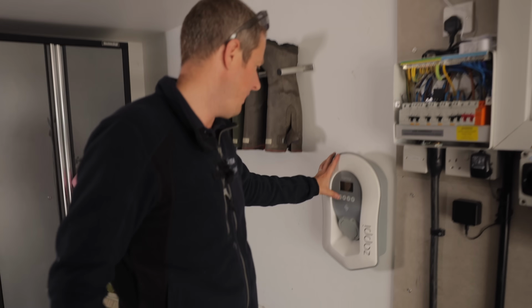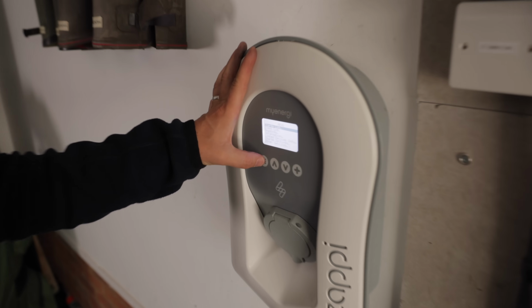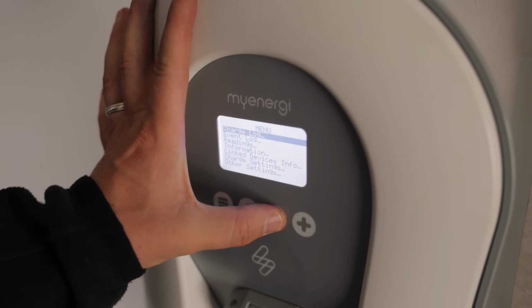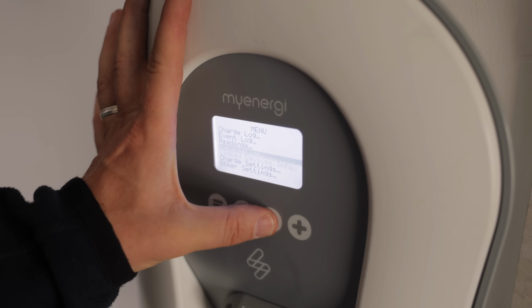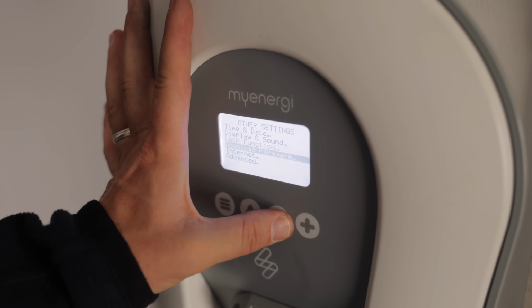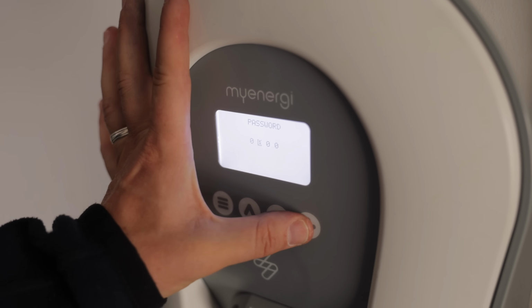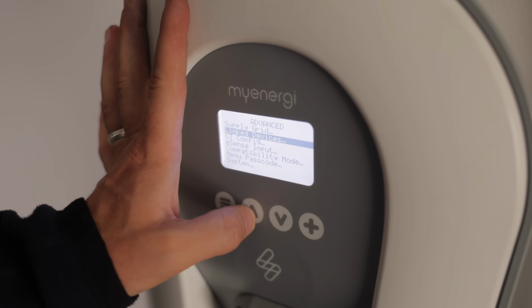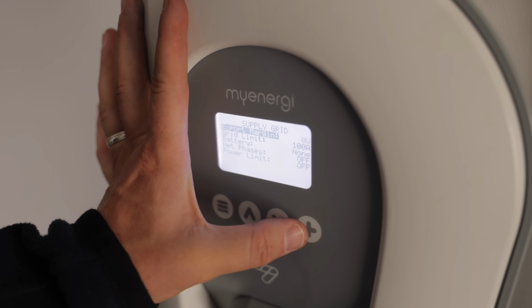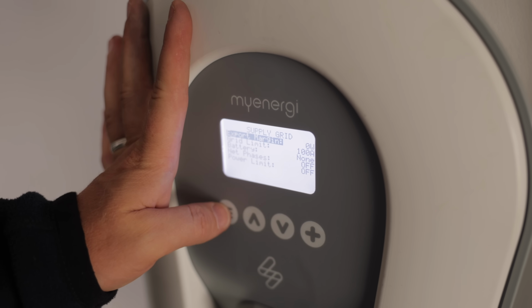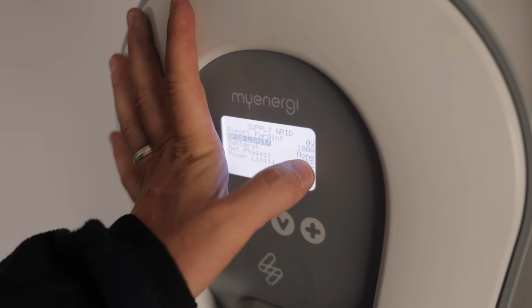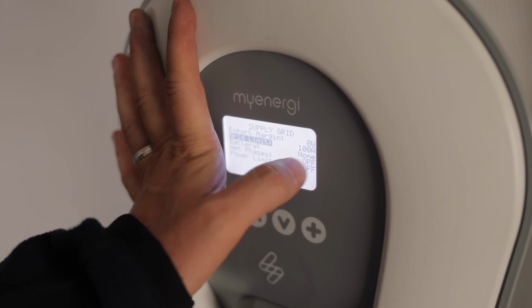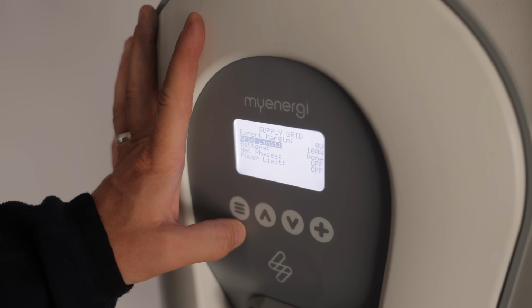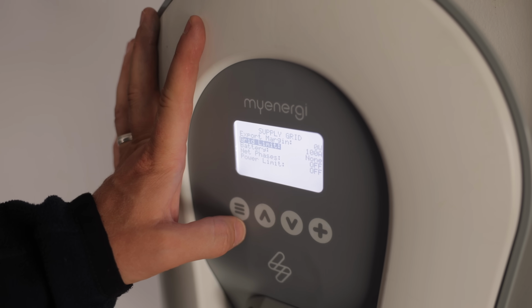So what you can do is in the master device, which in this case is the Zappi, you go to other settings, advanced, then you go to supply grid, network, and then grid limit, and you want to set that as the same as the main fuse. So here we have a grid limit of 100 amps already set, which is perfect.